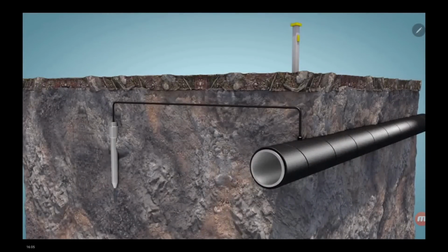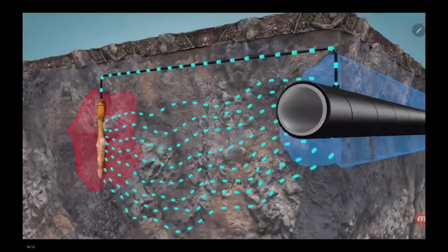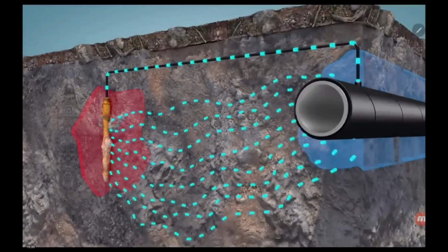Everything is calculated in cathodic protection by the corrosion specialists. We calculate all of this, gentlemen. This is to give you a general idea that this is a universe. A sacrificial anode, as I showed you earlier, this is how one works and how the currents are distributed in a sacrificial anode. Here you can see it deteriorates, it gets destroyed. We know when it will be destroyed, and the field measurements also indicate to us when this one has reached its lifespan, its useful operating life.